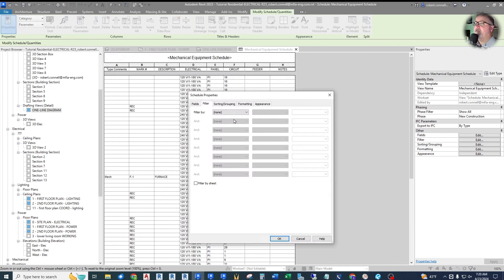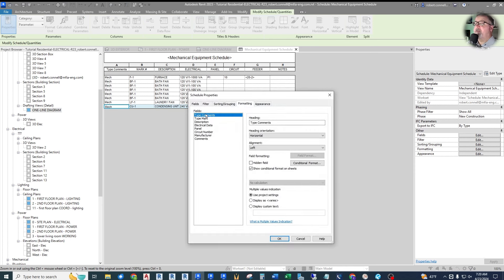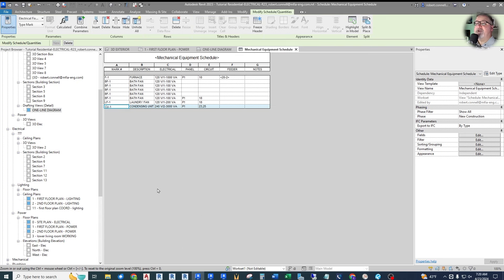Now with MECH applied to all equipment, we go back and apply our filter: Type Comments equals MECH. And now we have just our equipment showing. Finally, we don't need the Type Comments column to be visible since it's just used as a filter. Under Formatting, find Type Comments and check 'Hidden Field' — now it doesn't show but it's still being used to filter content.